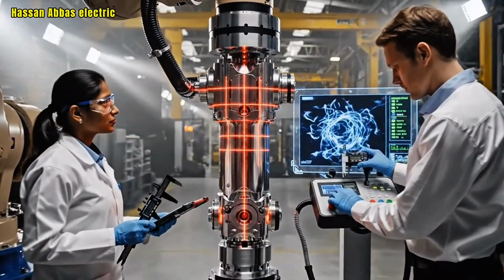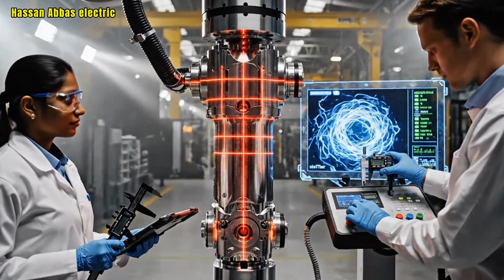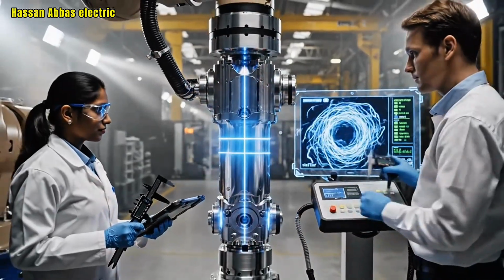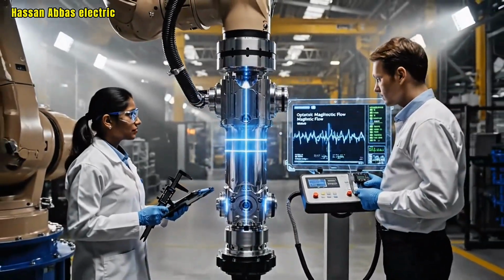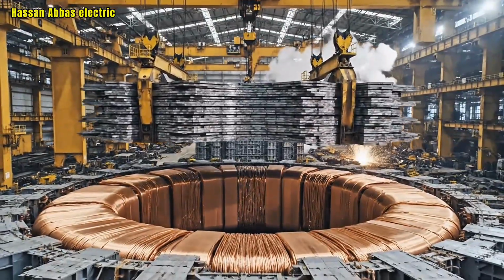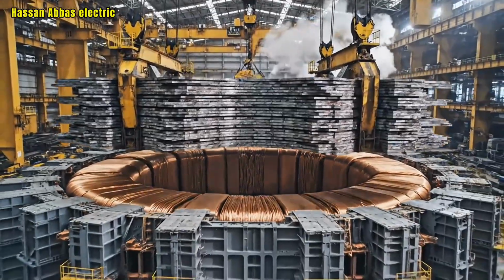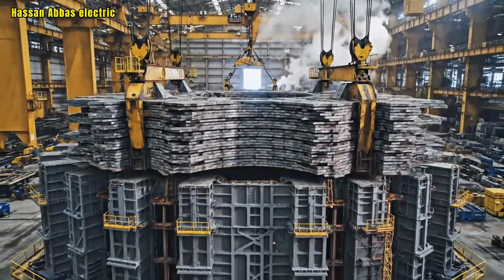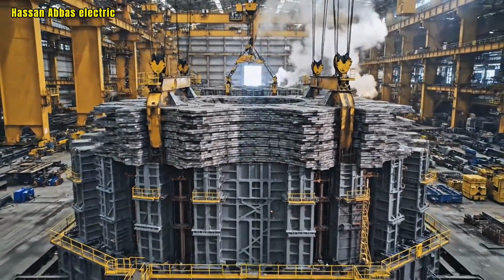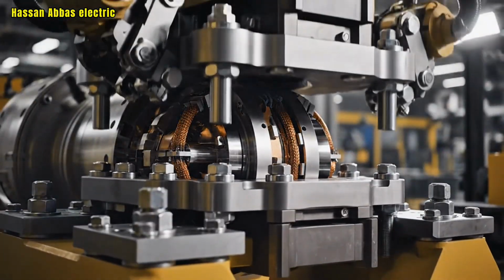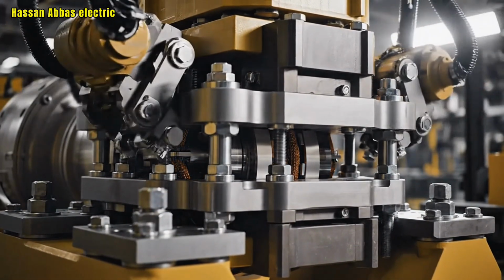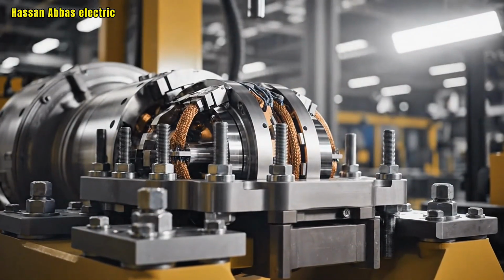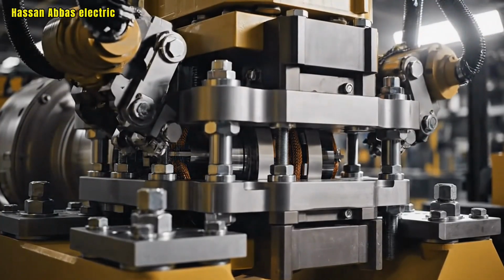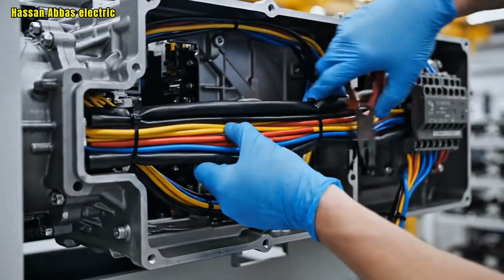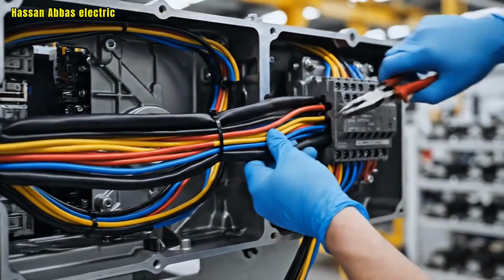Core limbs are aligned to ensure efficient magnetic flow. Upper core sections are installed to complete the magnetic path. The core is clamped tightly to prevent vibration and noise. Electrical leads are routed for external connections.